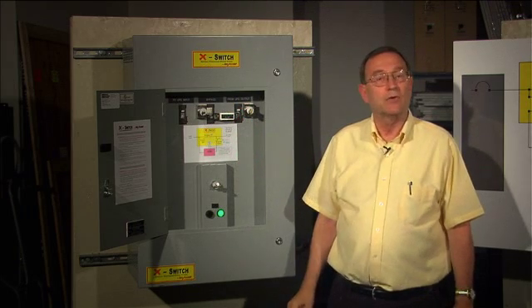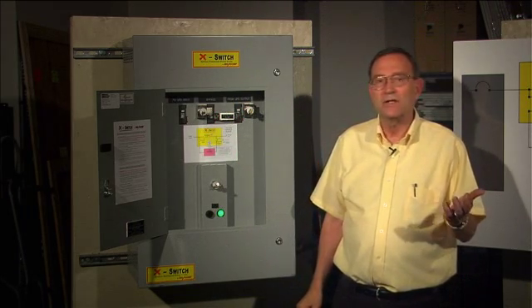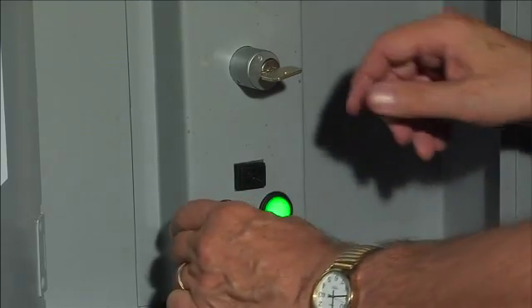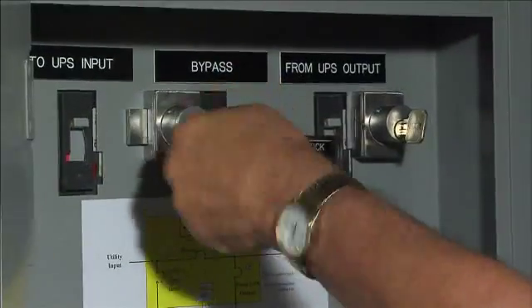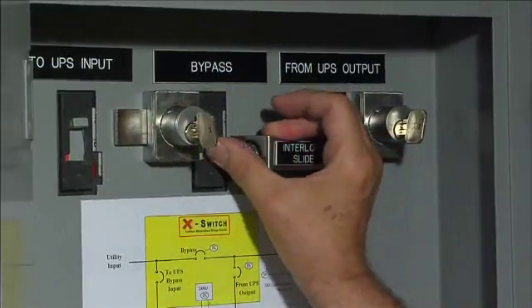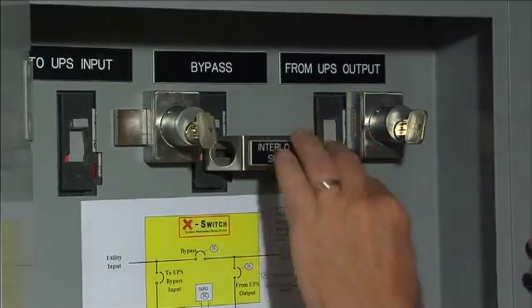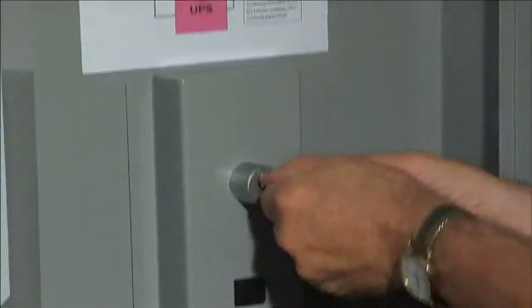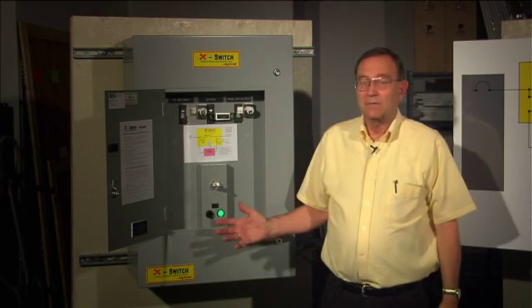Watch while I switch from normal operation to bypass. At each step, there's only one choice about what to do next. The green light is on, so that means it's safe to get the key. Now I can turn on the bypass breaker. Now slide the bar. Turn off the output breaker. Now I can lock it off and save the key for next time. The beeper reminds me to keep going — I'm not done yet.